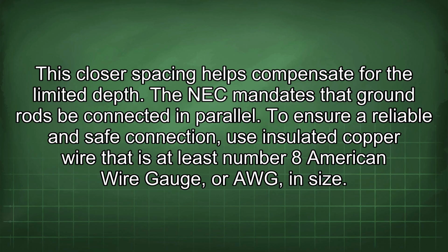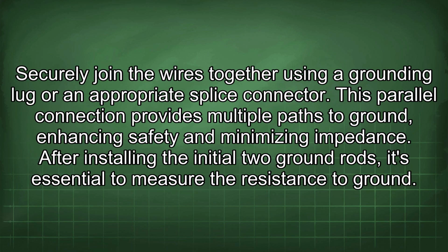The NEC mandates that ground rods be connected in parallel. To ensure a reliable and safe connection, use insulated copper wire that is at least number 8 American wire gauge, or AWG, in size. Securely join the wires together using a grounding lug or an appropriate splice connector. This parallel connection provides multiple paths to ground, enhancing safety and minimizing impedance.